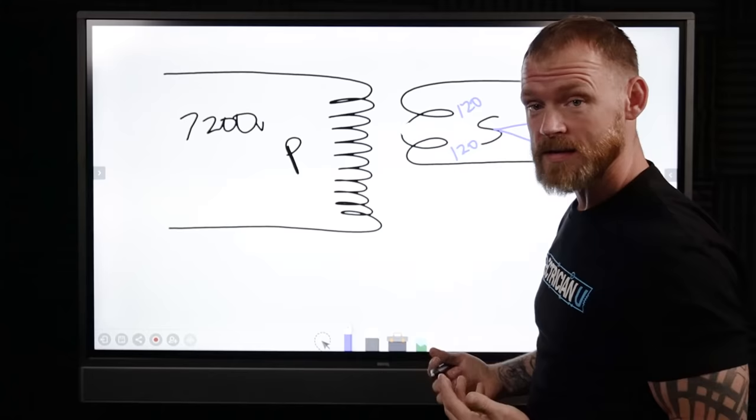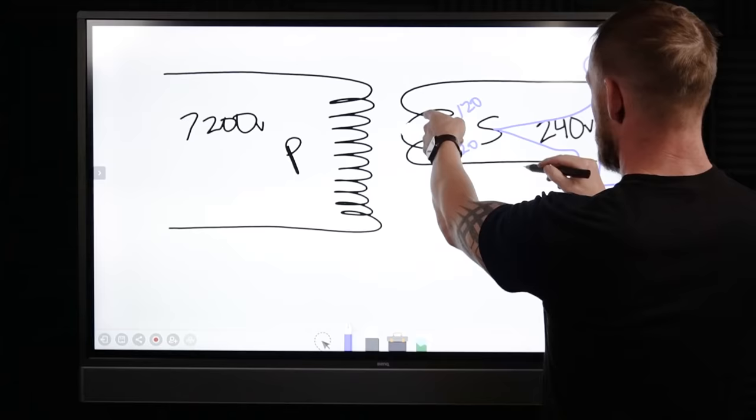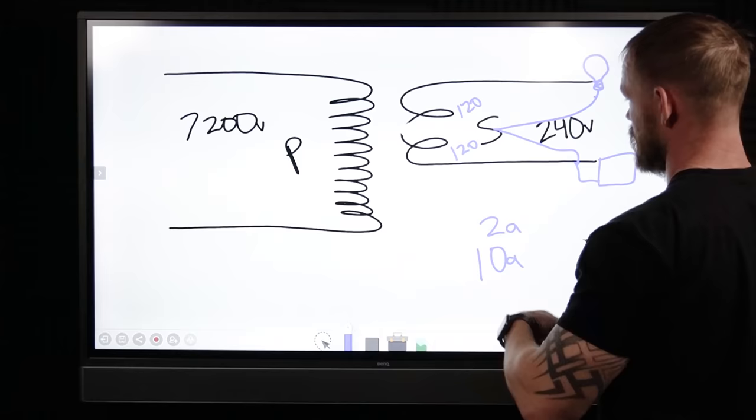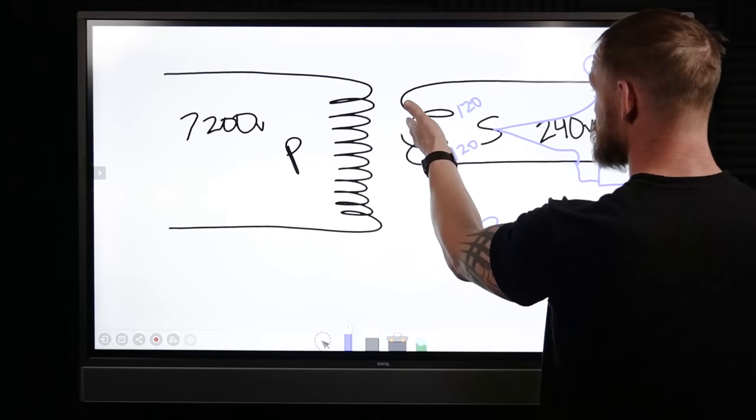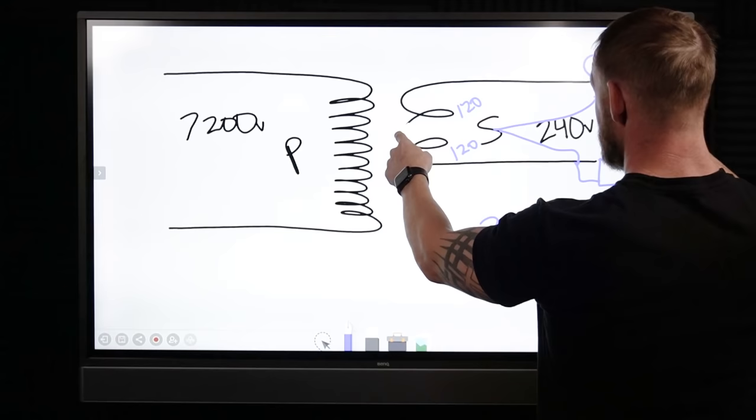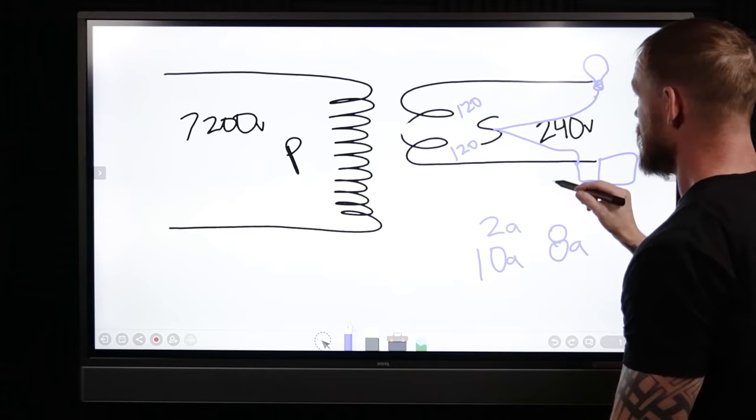So if our light bulb had like two amps flowing on this 120-volt side through the light bulb, but we've got 10 amps flowing through this circuit going through the microwave, then we have an imbalance that's happening. So the neutral is always going to carry whatever that imbalance is. We have to subtract those things, so we would end up having eight amps of current traveling on that neutral conductor.